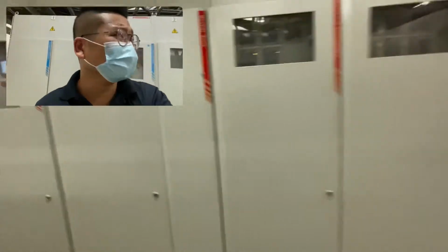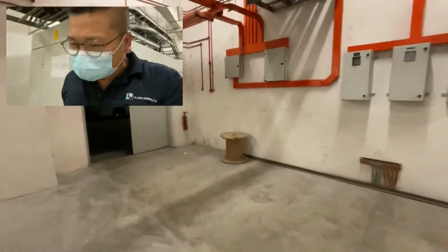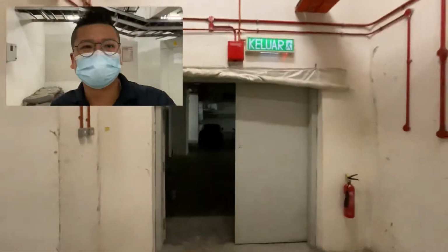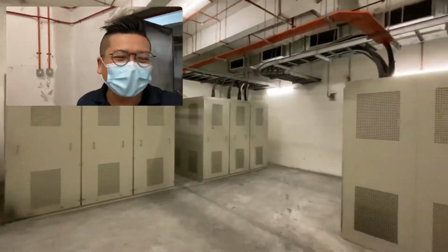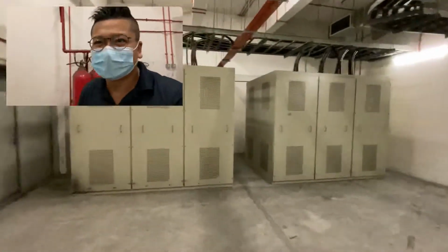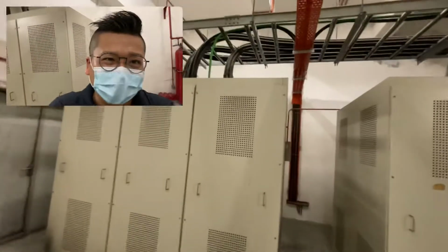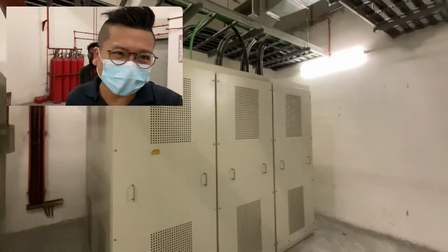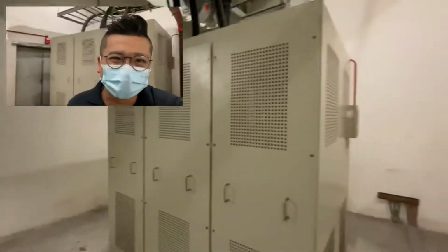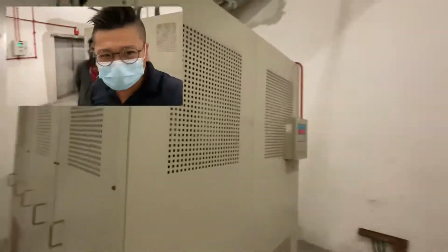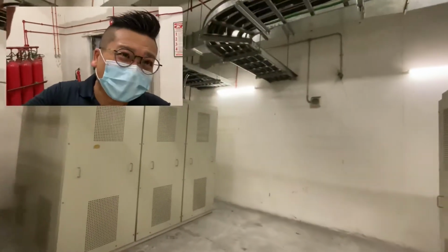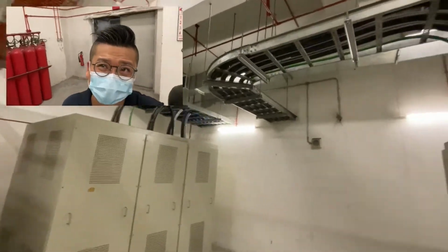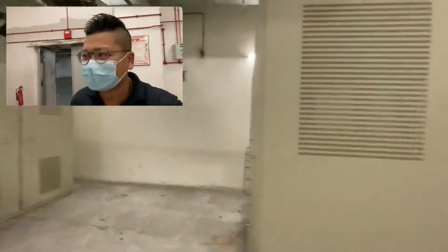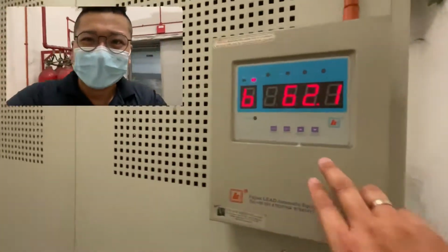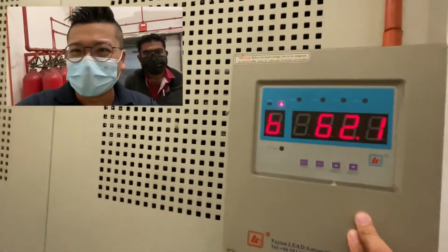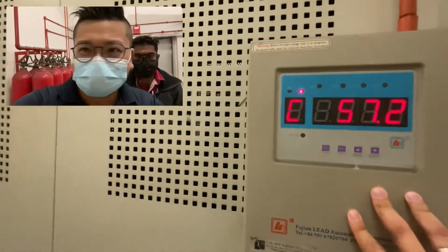Okay, now we go to the HV room and transformer room. Okay, I'm now at the transformer room. This is a tenant transformer, and this is a tenant transformer also. This is a common area transformer. First of all, we must make sure the room ventilation is in good condition. Currently it's running, there are ventilation. So we have to check the temperature. This is a common area transformer. It's for the owner side.